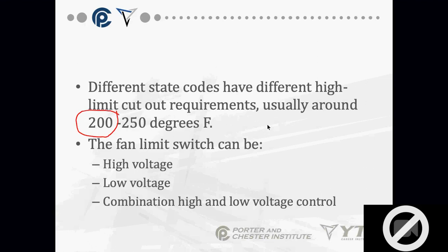Your furnace manufacturer will tell you what the high limit setting is. Don't go over what the furnace manufacturer has this set for. A lot of times they come preset with a screw in there so you can't move it. The fan limit switch can be high voltage, it can be low voltage, or it can be a combination of high and low voltage. Remember what I showed you yesterday on the schematics, that there are different ways to wire these things.